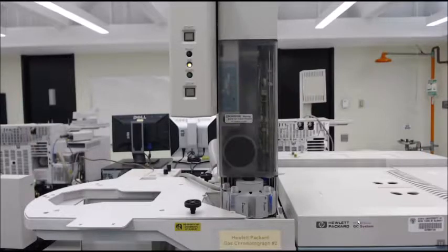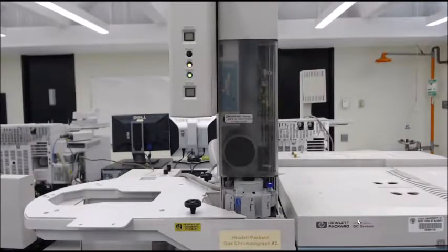The machine is now doing what's called pumping, which is to draw up sample and make sure there are no air bubbles. Air bubbles being injected into the small column will cause problems for the readings. Now that the sample's been deaerated, the needle should draw up sample and then inject it. There goes the injection.